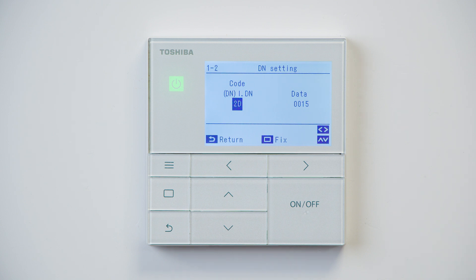This DN code is binary, so we can set this to a variety of settings including fan only, cooling only, dry mode, and heating only. We can also do a mix — for example, heating and cooling.